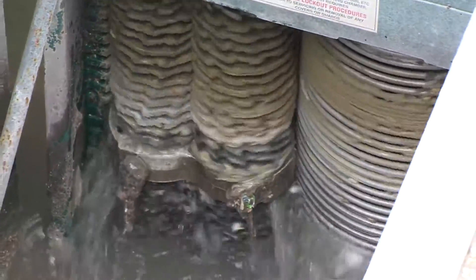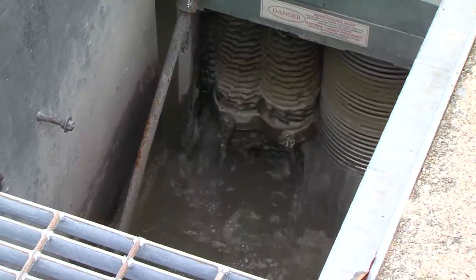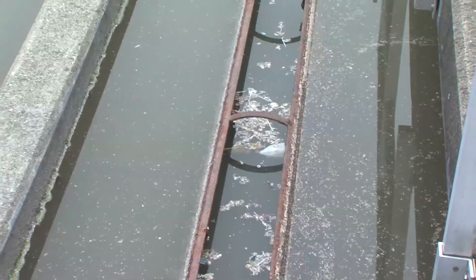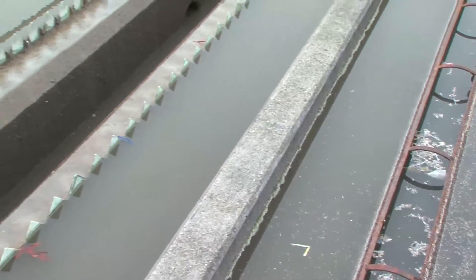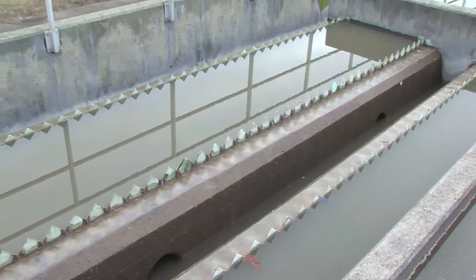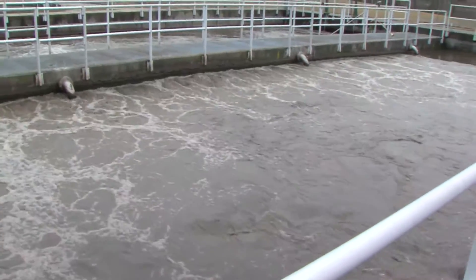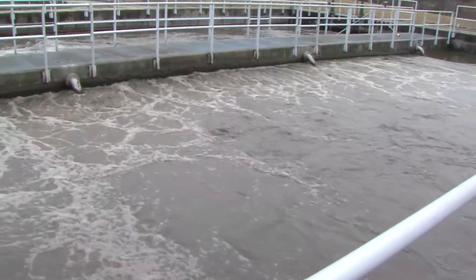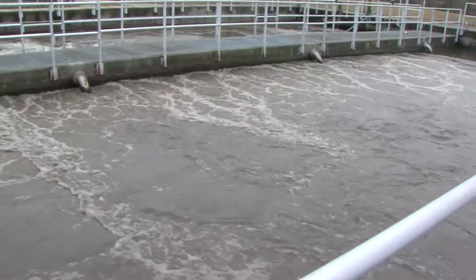After the grit chamber, the wastewater goes through the comminutor, which shreds large solids into smaller pieces. The wastewater then enters primary treatment. Primary settling basins are used to allow small solids to either settle out of the wastewater or float to the top. Once the wastewater has gone through primary treatment, it enters a secondary treatment process, which takes place in aeration basins.